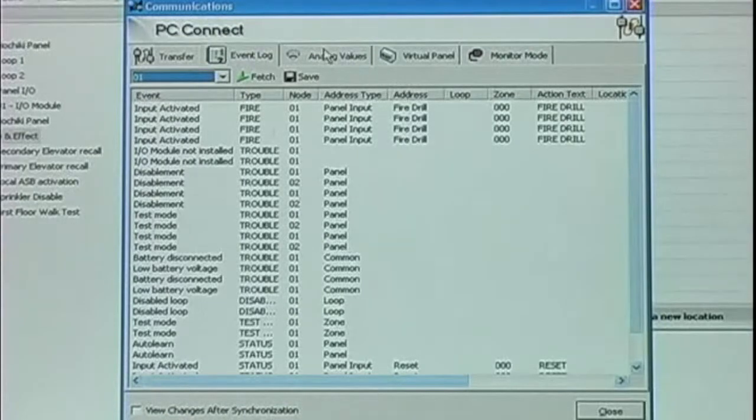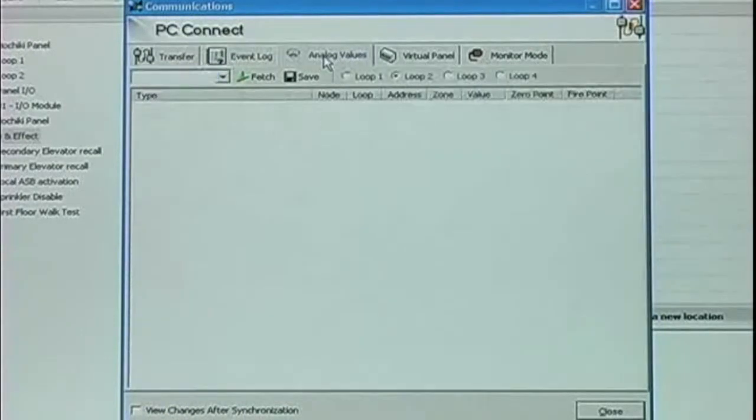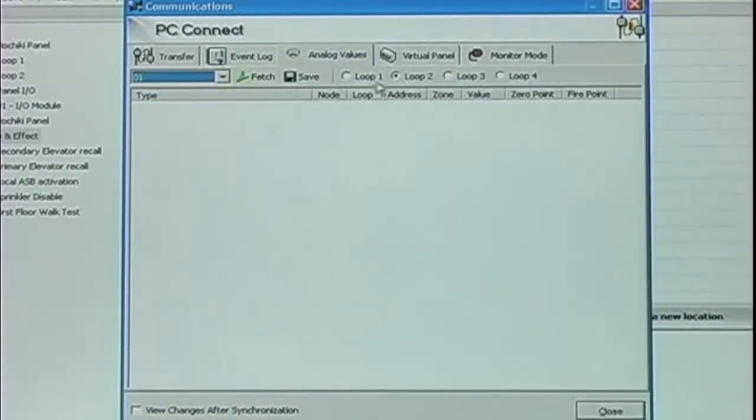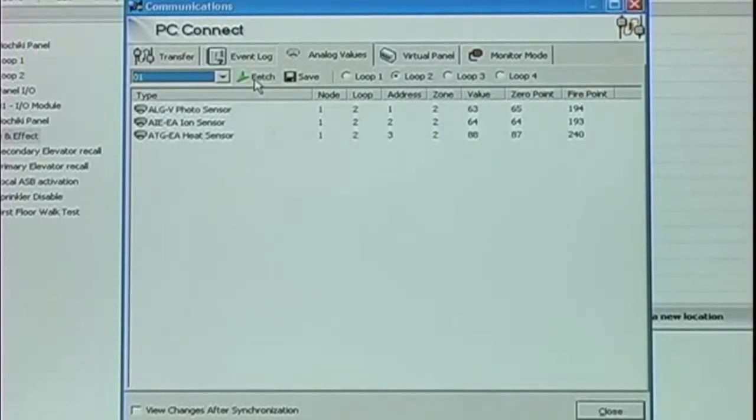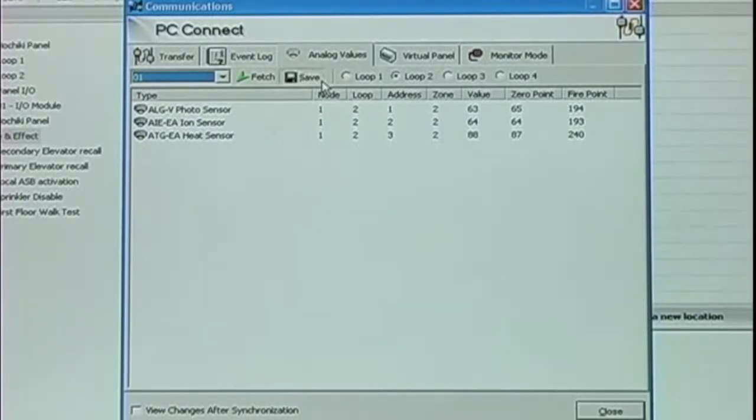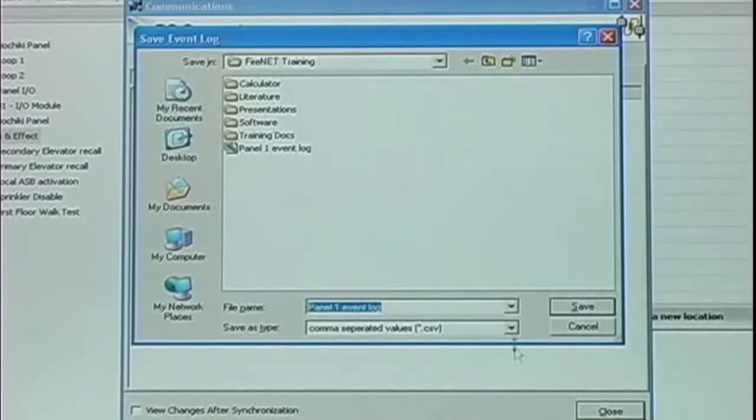The next tab is Analog Values. From here, we can select a node, select a loop, click Fetch, and upload the analog values of the sensors on that loop. As with the event log, we can save this out to a spreadsheet.